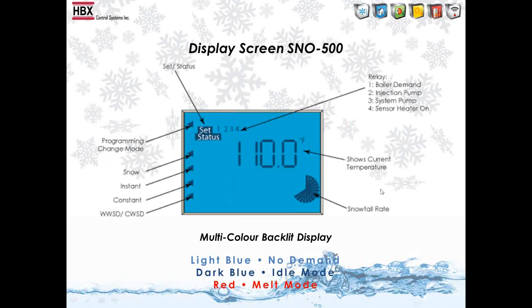So this is just a quick overview of the screen. So like I said, it's a single parameter screen, so it is an icon based screen. So up in the top we've got a set mode, status mode. If we're in programming, basically indicates snow, instant, constant, warm weather, and cold weather shutdown is this arrow. Here's your temperature reading, and then it'll actually give you the snowfall rate here as well. And then the 1, 2, 3, 4 across the top is obviously if we have boiler demand, the injection pumps on, system pumps on, or the heater is on.